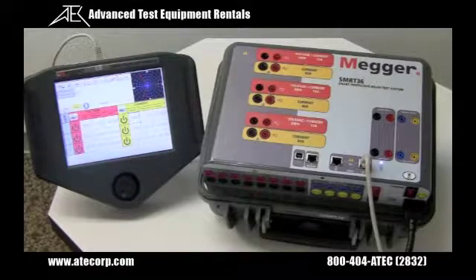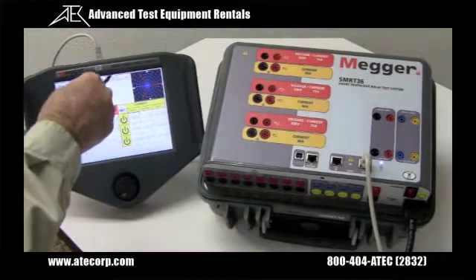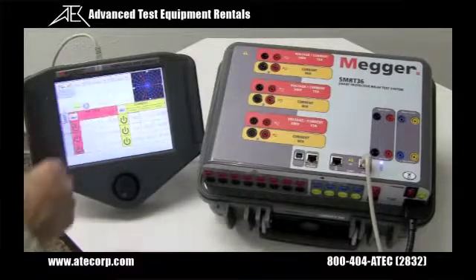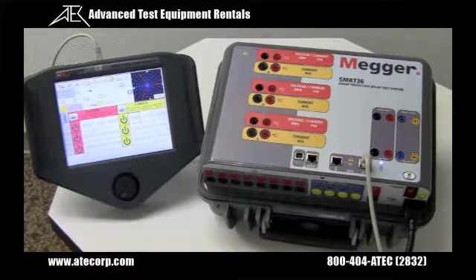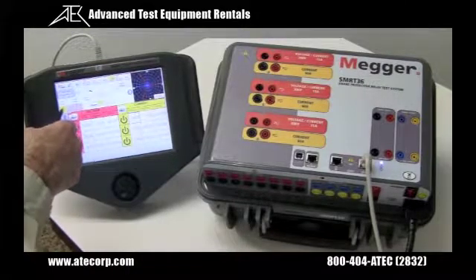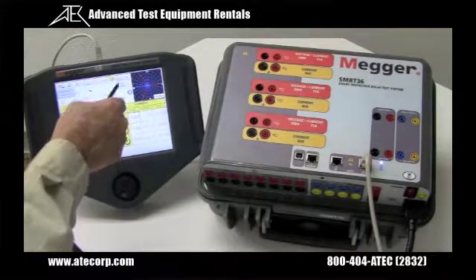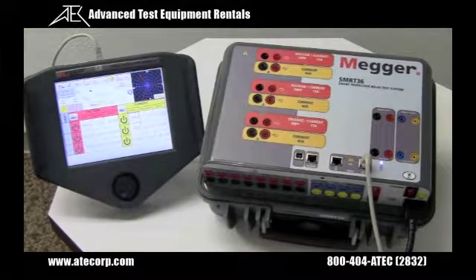The new STVI has automatic ramp, pulse ramp, and new binary search pulse ramp. By clicking on the automatic ramp, the user will have a selection of step ramp, pulse ramp, and binary search pulse ramp. We also have a built-in ramp wizard for testing electromechanical, both instantaneous and time overcurrent delays.